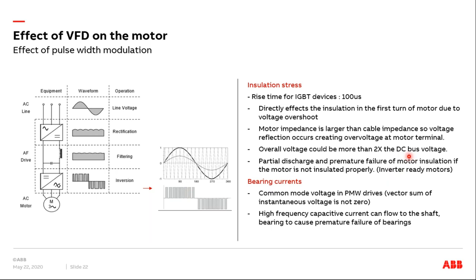That would stress your insulation. It's not an immediate failure, but slowly, because of partial discharges, you will prematurely fail the motor. You need to be aware that you need to have an inverter ready motor to use with a drive, so that the lifetime rated by the manufacturer can be achieved. Otherwise, it might fail earlier.